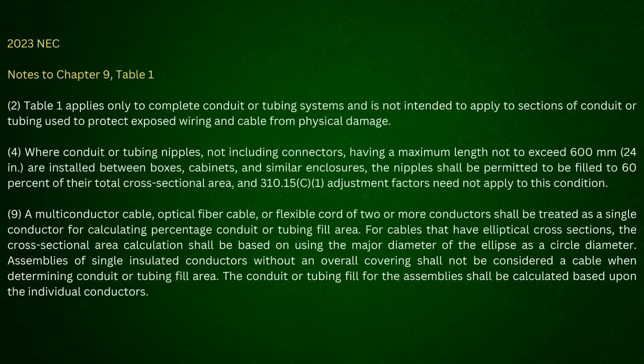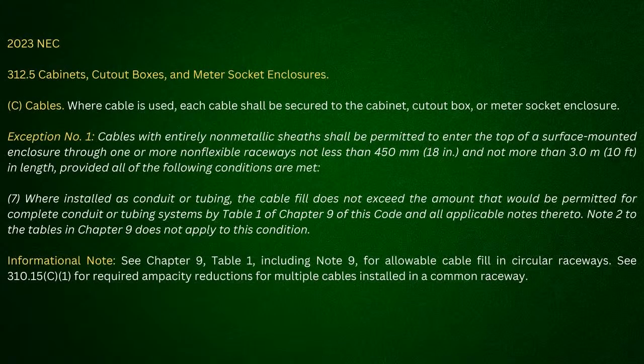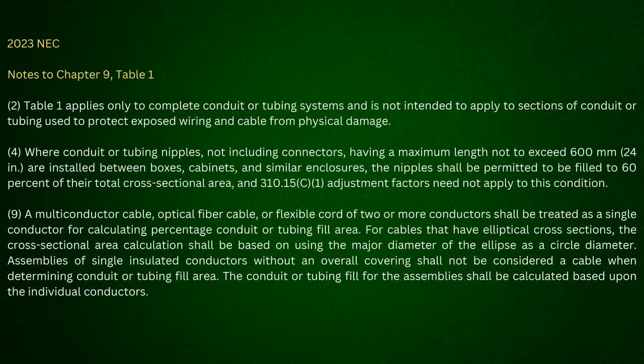Now, it also said, when I come back here and I look at the informational note, it says see note 9 for allowable cable fill in circular raceways. And then it says see 310.15C1 for required ampacity reductions for multiple cables installed in a common raceway. So it has to be a raceway. That's why it's telling you here in number 7 that this applies to what? Chapter 9, Table 1 and Note 2 doesn't apply to this type of condition because why? It's being used as a sleeve. Okay? Now, if anybody's watching, tell me in the comments where you disagree with what I just stated.